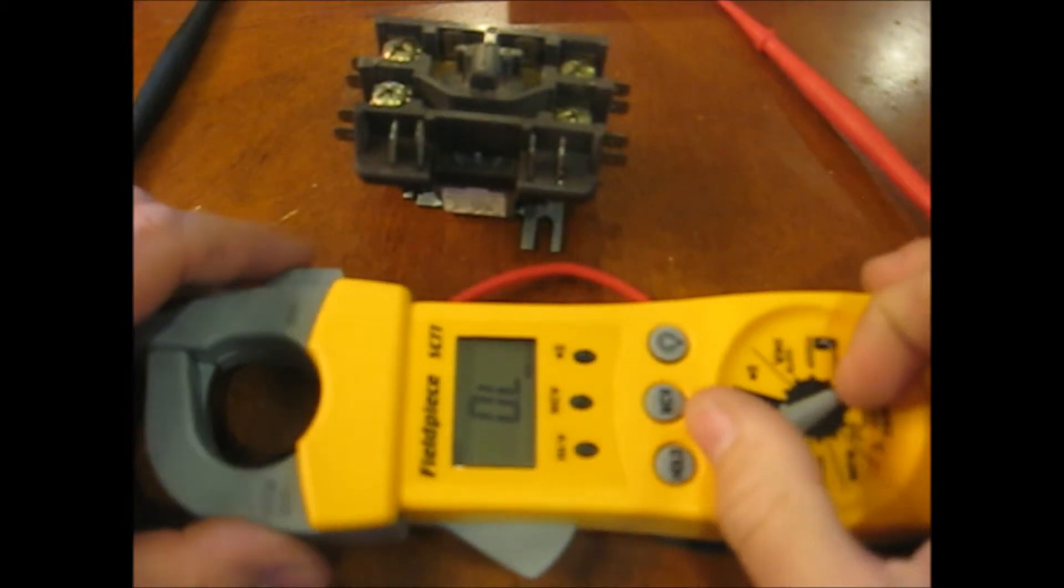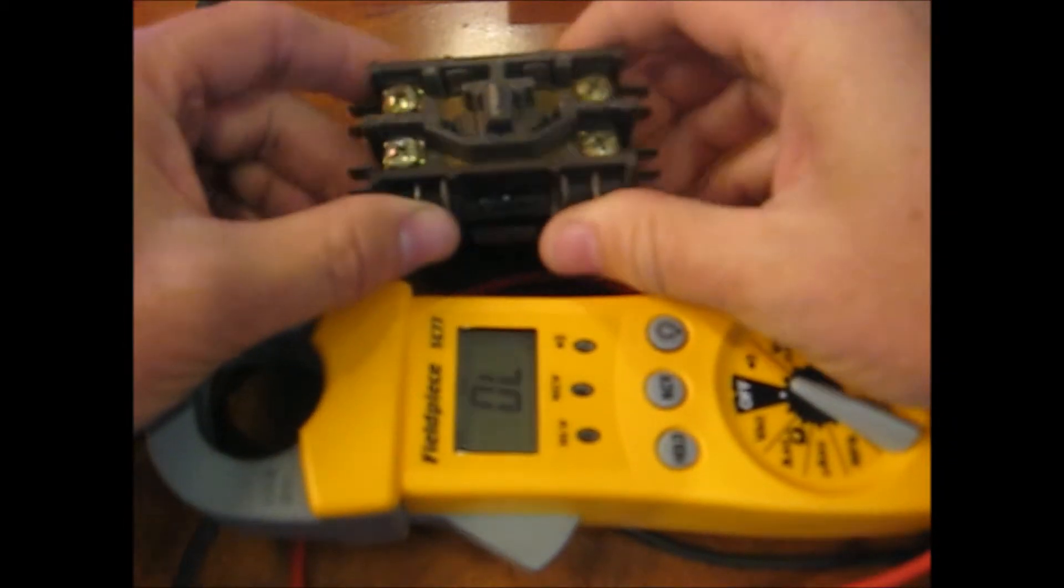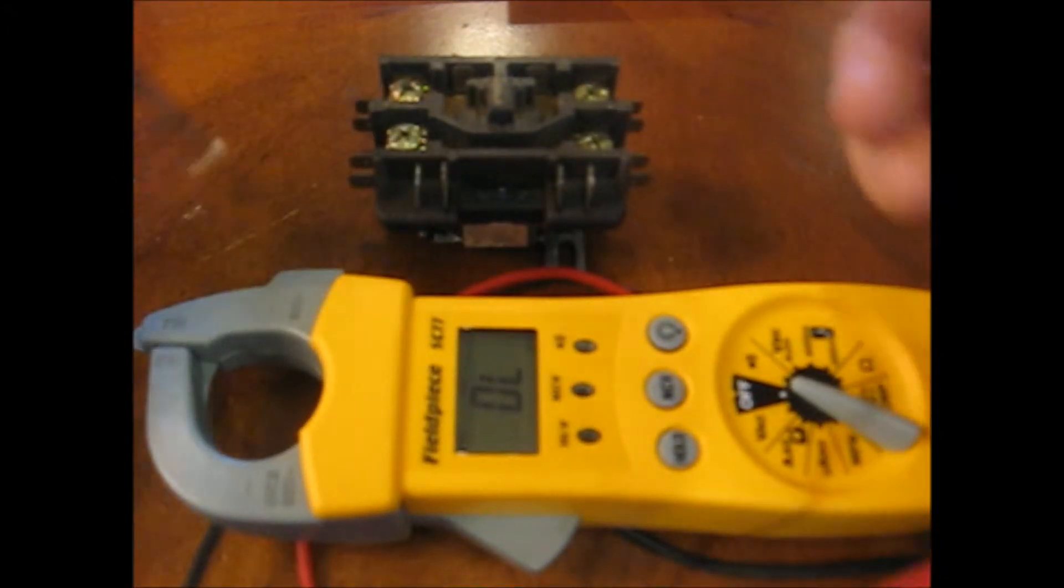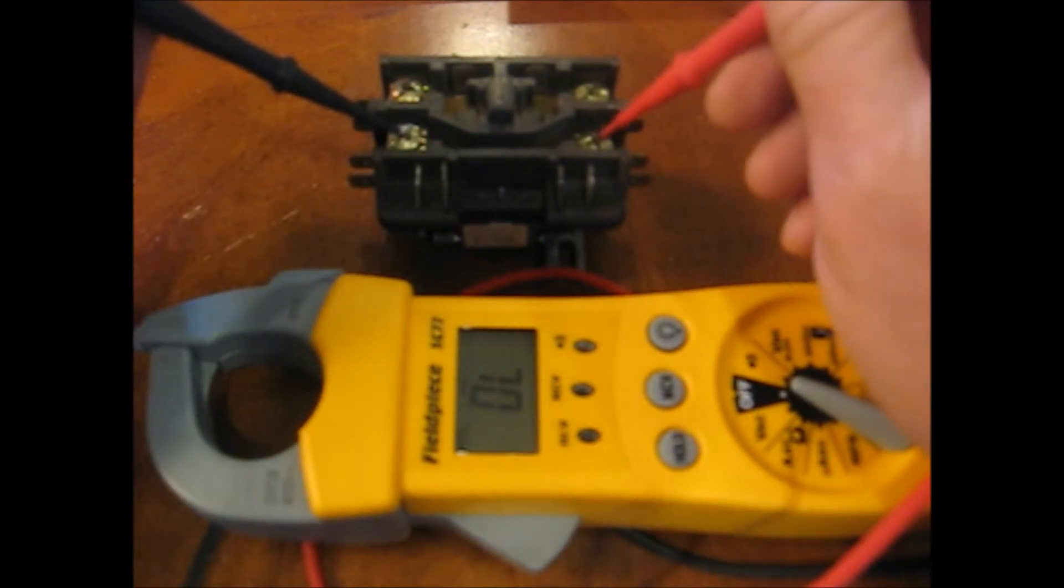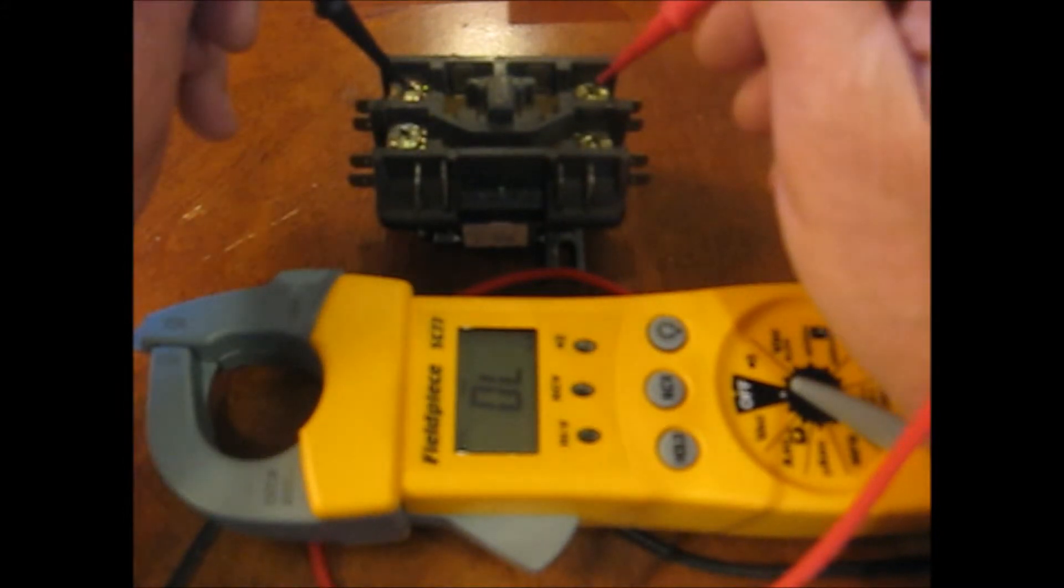Let's go back to continuity here. I'm going to show you what we mean by the single poles now. This is the line side and the load side. So we have continuity across there. And this is the other line and load. And notice we have no continuity until we press in the switch.